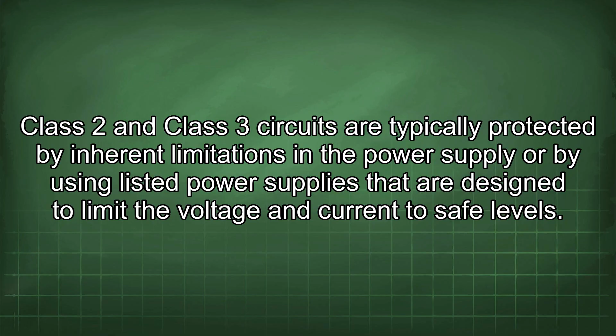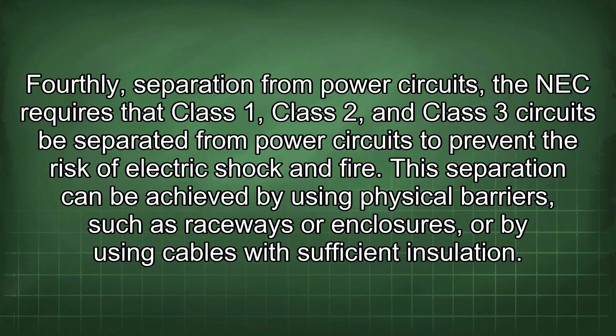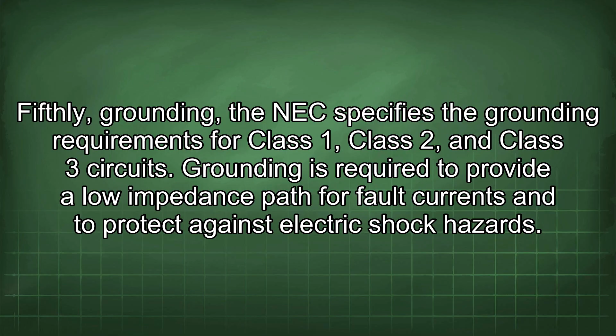Fourthly, separation from power circuits. The NEC requires that Class 1, Class 2, and Class 3 circuits be separated from power circuits to prevent the risk of electric shock and fire. This separation can be achieved by using physical barriers, such as raceways or enclosures, or by using cables with sufficient insulation. Fifthly, grounding. The NEC specifies the grounding requirements for Class 1, Class 2, and Class 3 circuits. Grounding is required to provide a low-impedance path for fault currents and to protect against electric shock hazards.